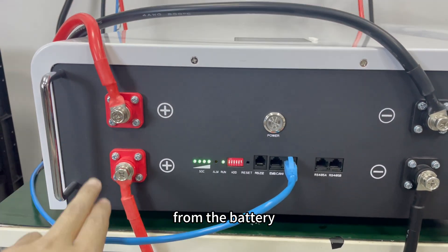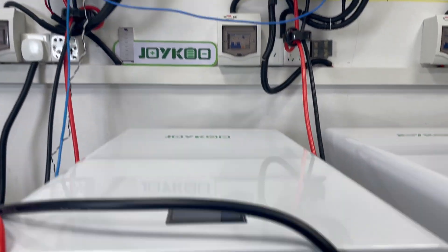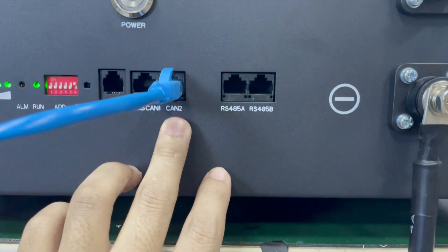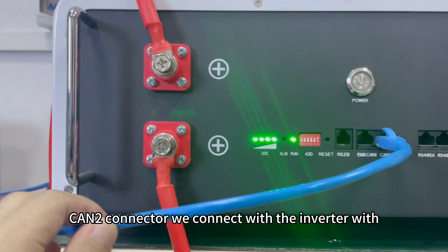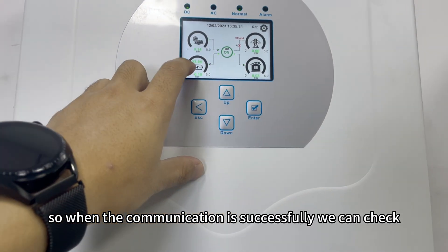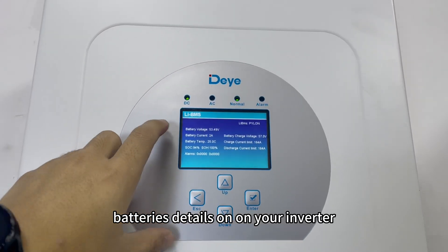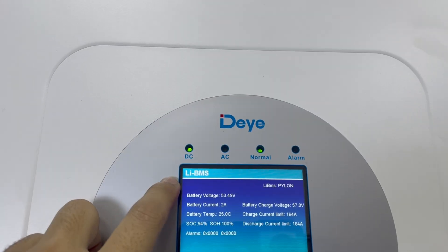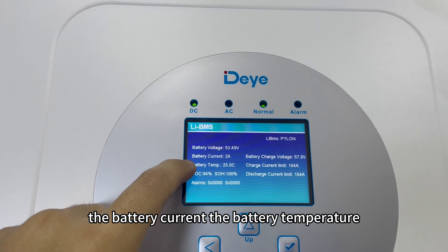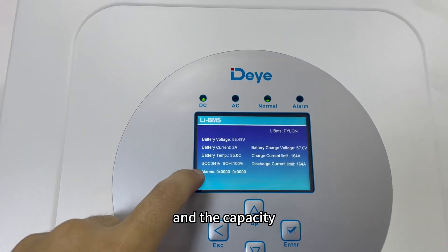From the battery, negative and positive connect to the solar inverter. The DIP switch number six is set to on, and we use the CAN2 connector to connect the communication cable to the inverter. When communication is successful, you can check the battery details on the inverter display — including the battery voltage, battery current, battery temperature, charge and discharge current limits, and capacity.